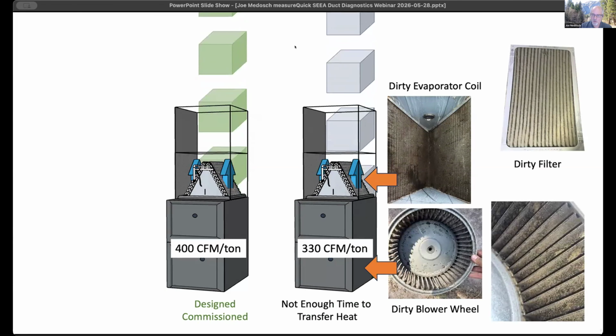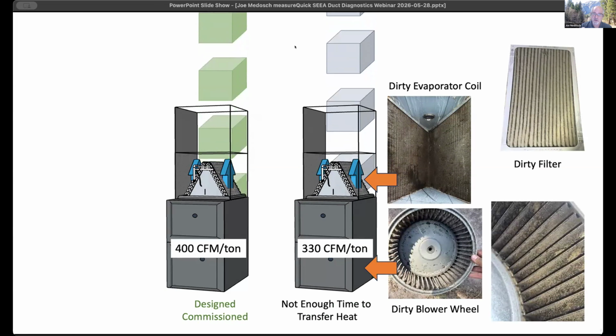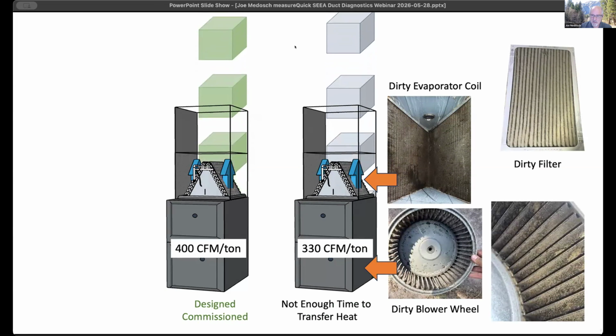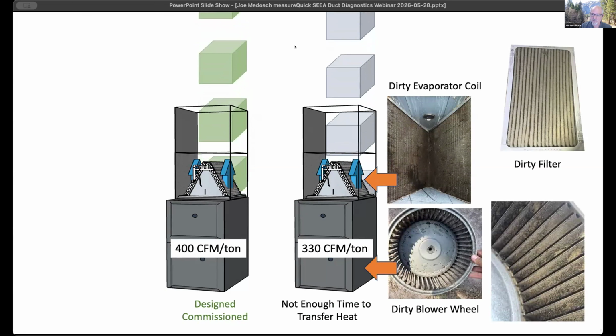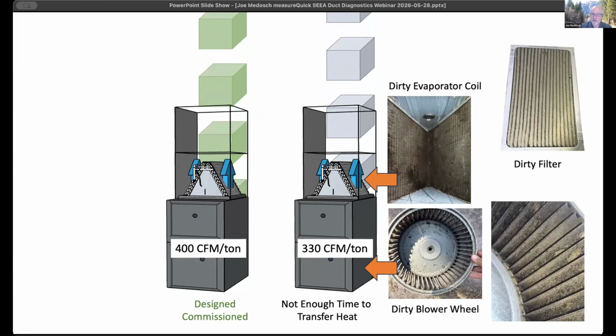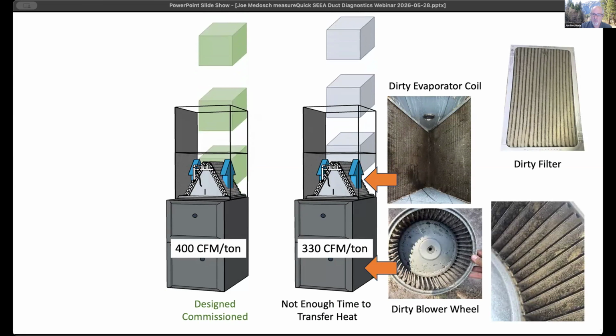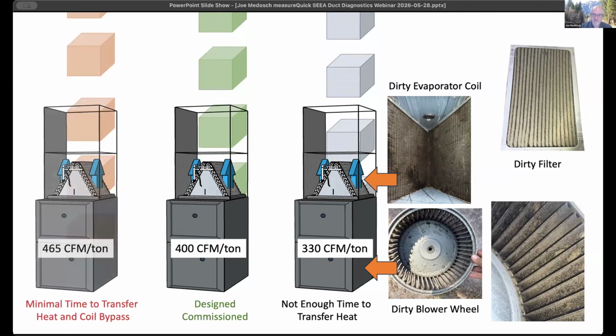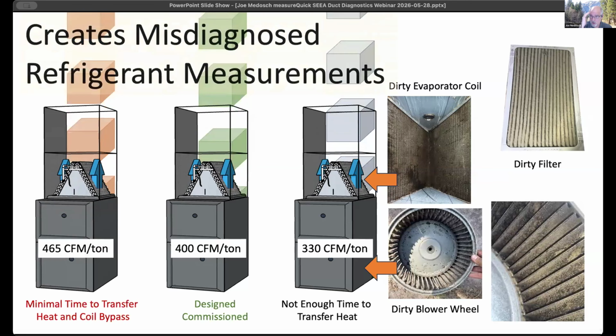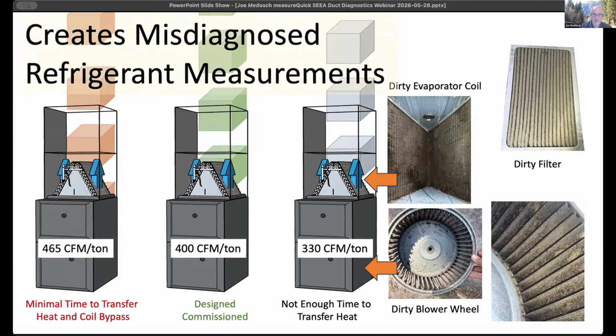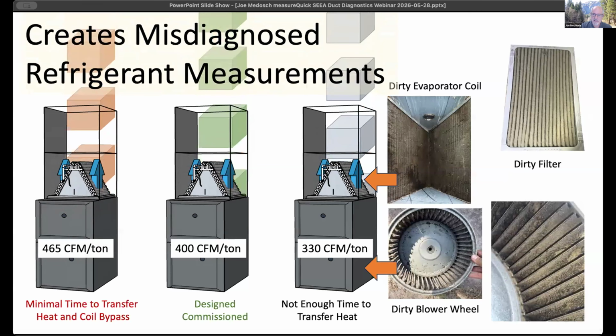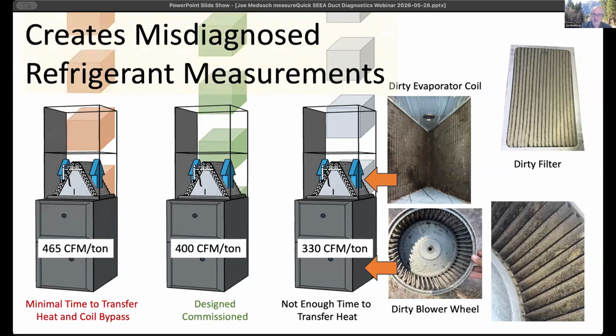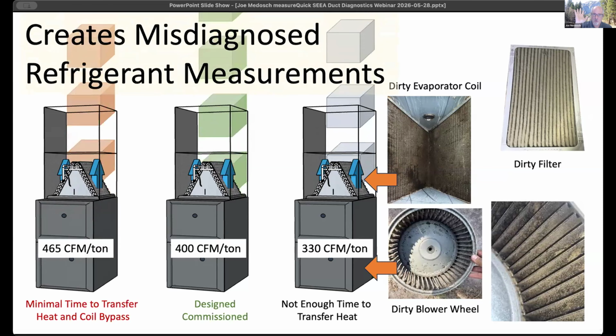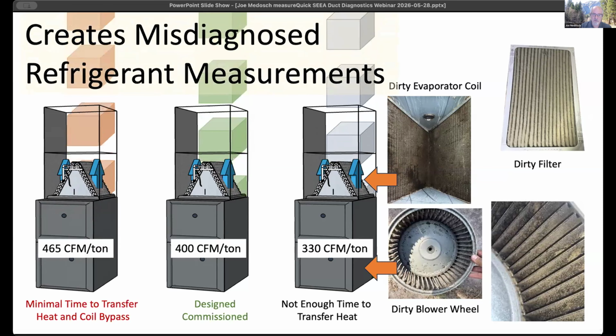So I have a dirty blower wheel, I've got a dirty coil, I've got a dirty filter. All of these things are going to slow your airflow down, and they're going to cause problems, not just system-wide with your airflow, but they're going to show up dynamically. And the other one would be if somebody set the speed wrong. There's a long list of stuff that could be happening with the wrong motor, wrong settings, a variety of stuff that wasn't done initially, but people felt that there was cold air or hot air and they just ran out the door and all was good.